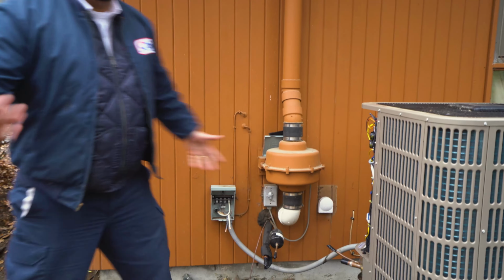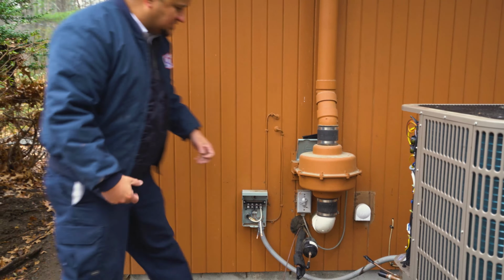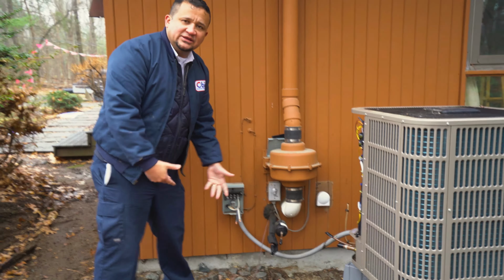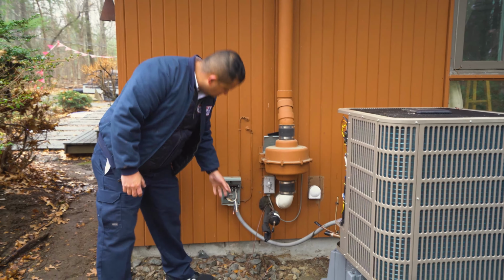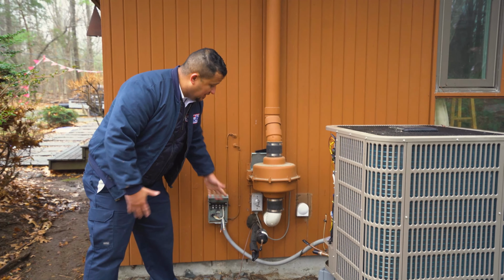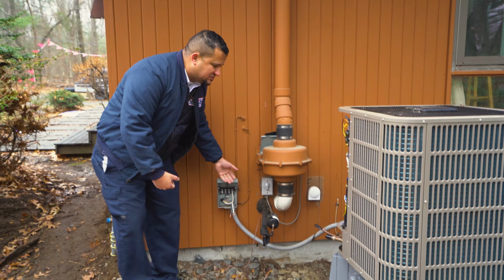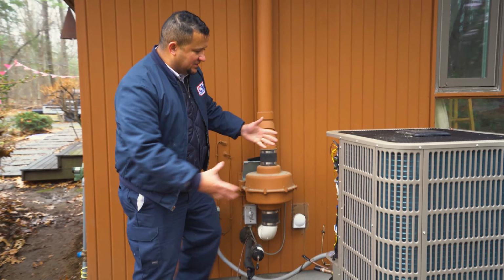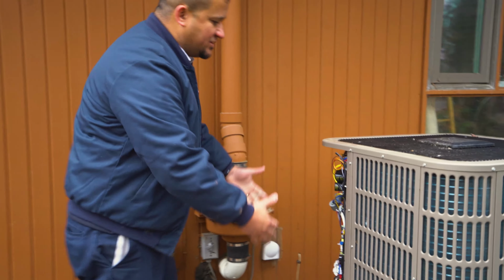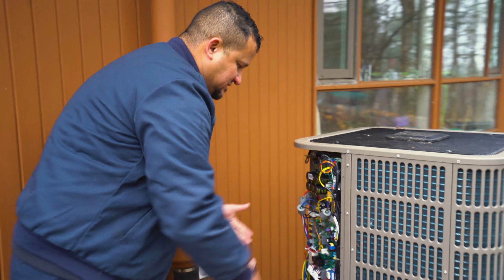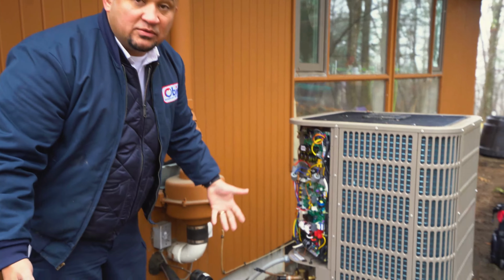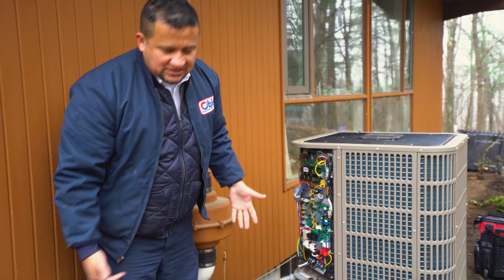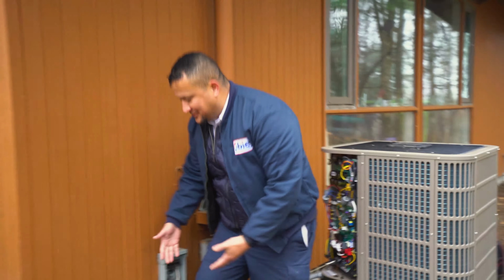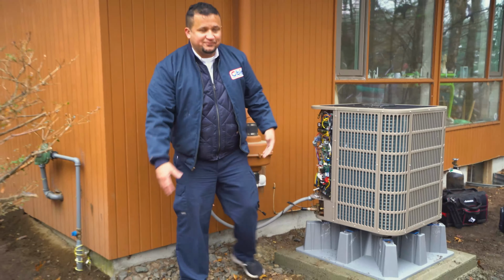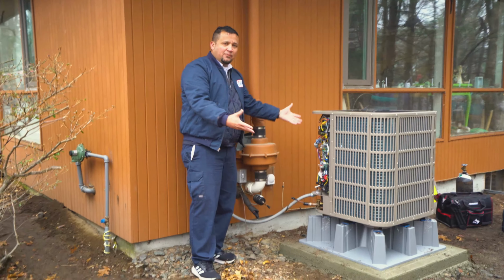Another problem is that by code, this disconnect should never be behind the unit. If you need to turn it off, you just come in here and pull this off. And if it's behind the unit, you have no space. It's the same thing in here. This should be in a place where you can work on it, so you have access. If this is behind and the way it was before, you can't, because a guy like me is not going to fit behind here. So for safety, that should be in an open space.